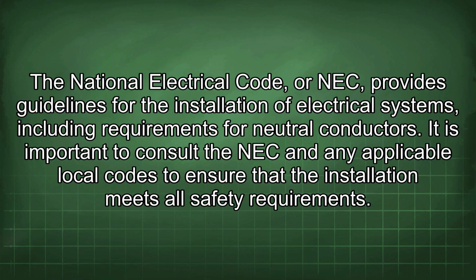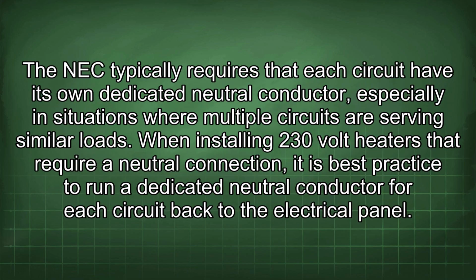The National Electrical Code, or NEC, provides guidelines for the installation of electrical systems, including requirements for neutral conductors. It is important to consult the NEC and any applicable local codes to ensure that the installation meets all safety requirements. The NEC typically requires that each circuit have its own dedicated neutral conductor, especially in situations where multiple circuits are serving similar loads. When installing 230-volt heaters that require a neutral connection, it is best practice to run a dedicated neutral conductor for each circuit back to the electrical panel.